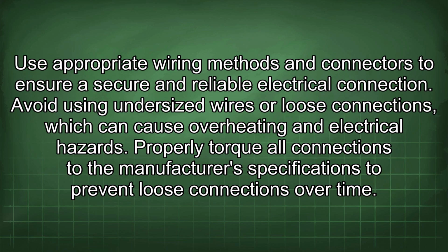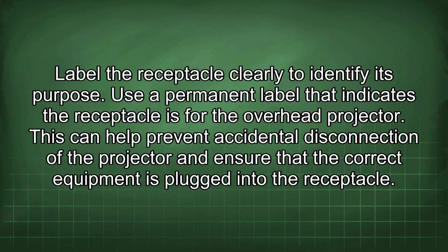Use appropriate wiring methods and connectors to ensure a secure and reliable electrical connection. Avoid using undersized wires or loose connections, which can cause overheating and electrical hazards. Properly torque all connections to the manufacturer's specifications to prevent loose connections over time. Label the receptacle clearly to identify its purpose. Use a permanent label that indicates the receptacle is for the overhead projector. This can help prevent accidental disconnection of the projector and ensure that the correct equipment is plugged into the receptacle.